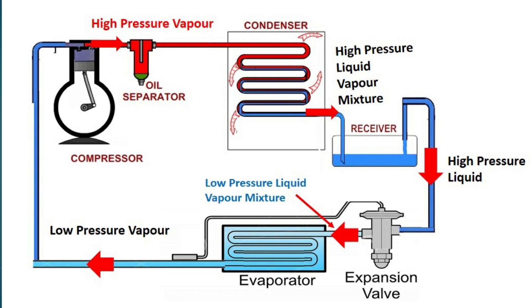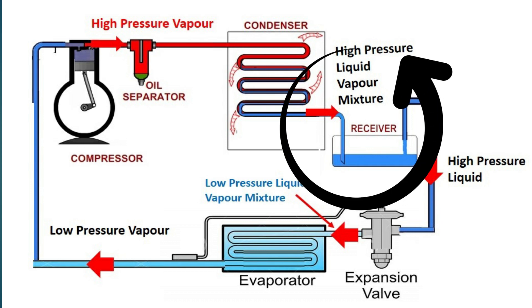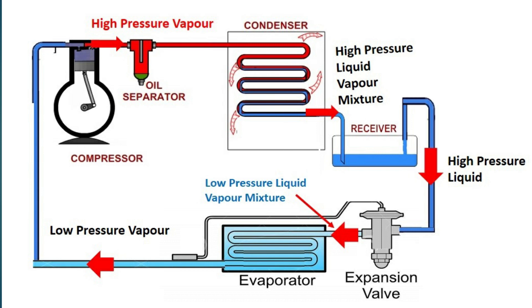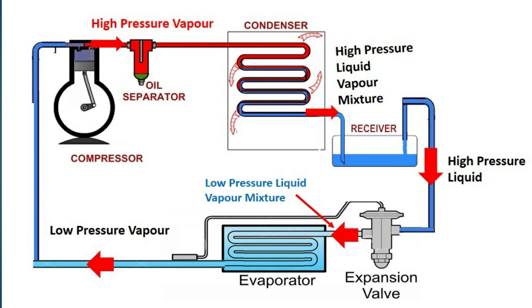The function of the compressor is to compress the refrigerant. This refrigerant passes through the condenser, which rejects heat to the surroundings. After that, it collects into the receiver. The receiver collects the refrigerant, then it expands through the expansion valve. The function of the expansion valve is to expand the refrigerant, so here the liquid-vapor refrigerant at low pressure enters into the evaporator — our freezer.